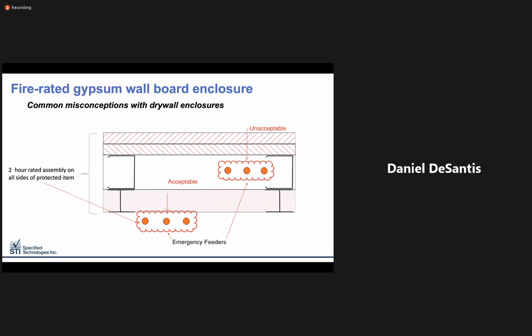One of the biggest misconceptions that we see in the field is the belief that running a conduit inside the stud cavity of a rated wall will provide a rating. This simply isn't the case. In the event of a fire, the exposed side of the shaft will be sacrificed. The outer layer of gypsum will burn away early on. This is by design. The entire assembly may be rated for 2 hours, but running services within the stud cavity will not get you a rating at all. In fact, the temperatures within the stud cavity will rise within minutes, while the unexposed side may remain unaffected for considerably longer.